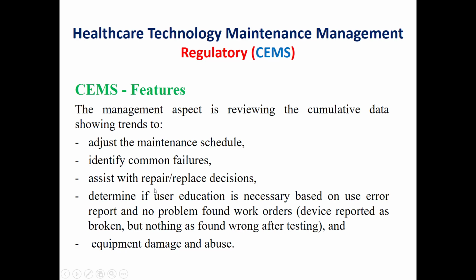Assist with repair and replace decisions. Sometimes when the cost of the repair will be a little bit higher by comparison to the initial cost, then a repair or replace decision will be taken, and the disposal of this medical device should be done. So this will be provided through the gathering of the information about this device, and this will be through the computerized equipment management system.